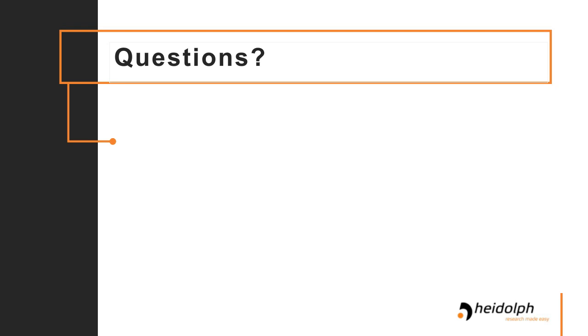That's a very good question. I've run into this one myself, actually. Basically, what's happening is you're evaporating off that low boiling point solvent just fine. And then to get to that high boiling point solvent, you have to reduce your vacuum pressure significantly further, especially if you are keeping your heating bath constant.